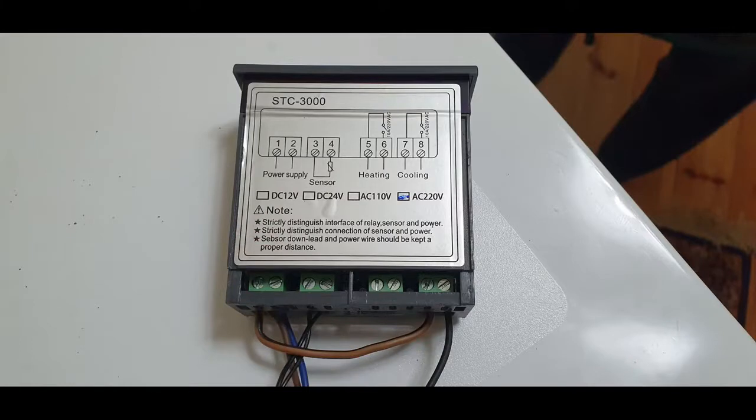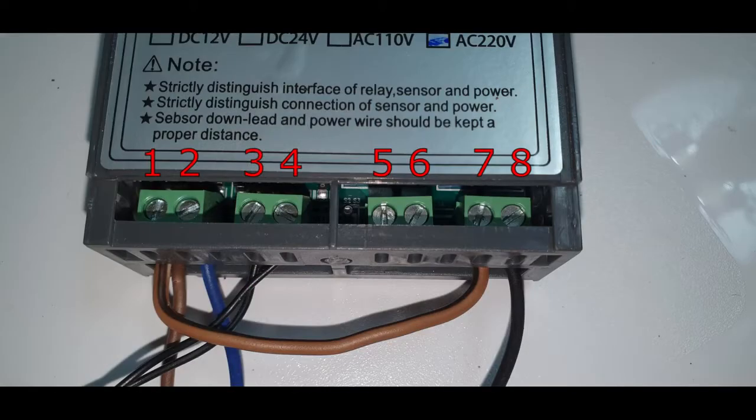We switch the connections between the old controller and the new one. The phase and neutral are connected as a power supply to the controller in ports 1 and 2. The temperature sensor is connected to ports 3 and 4.